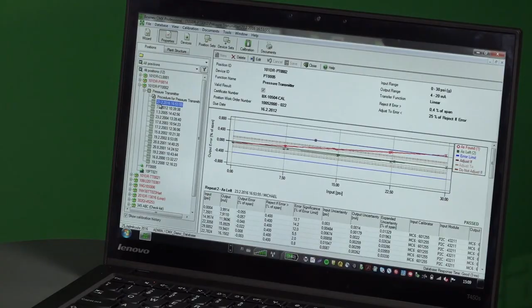It's very important to point out at this stage that every calibration is done in the same way. This is a huge advantage of using CMX. All the technicians follow the same procedures. Upon receiving back to the CMX, you go to the position that you've just calibrated and received information for. You go to the latest results, and you can right now see as found, as left, whether it's passed or not. You can see the tolerances, the intervals, all the important information. You can keep it here, or you can print the certificate. It all depends what you need.